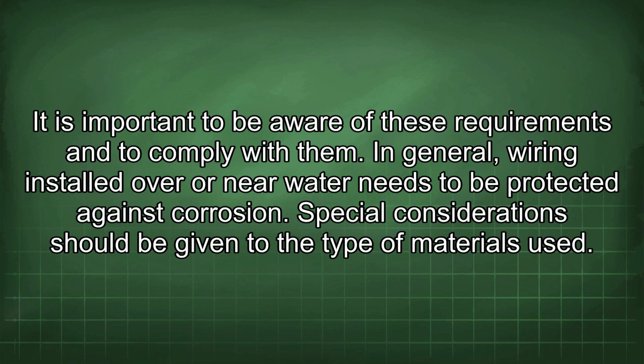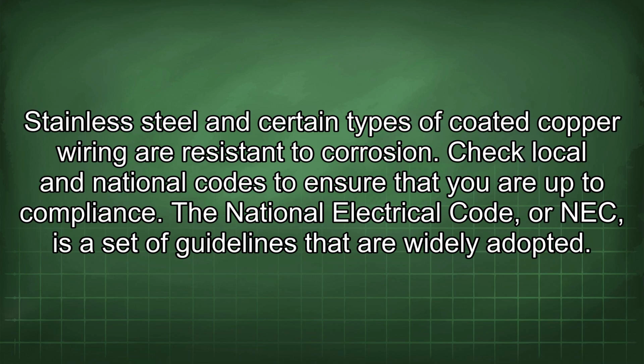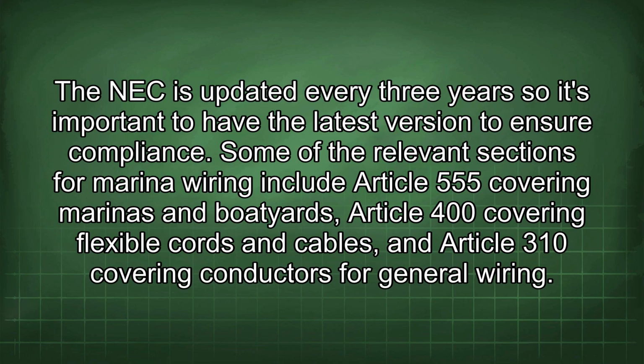In general, wiring installed over or near water needs to be protected against corrosion. Special consideration should be given to the type of materials used. Stainless steel and certain types of coated copper wiring are resistant to corrosion. Check local and national codes to ensure that you are in compliance. The National Electrical Code, or NEC, is a set of guidelines that are widely adopted. The NEC is updated every 3 years, so it's important to have the latest version to ensure compliance.